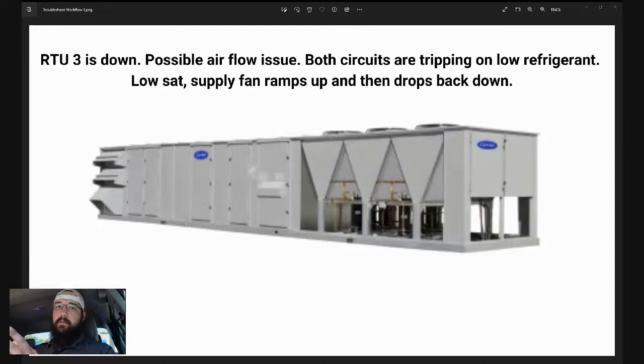And then they went around and checked the blower fan, and the whole fan deck was really cold. Now the system had shut off at this point, and from what I understand, I don't believe the fans were actually running when they got to it. I don't know if they power cycled it or what. Either way, their feedback was that it was really cold in the supply cabinet, and because of that, he believes that may be evidence of a fan issue. So, dealing with low saturation.